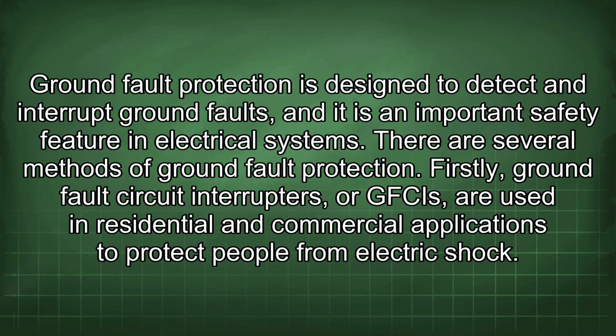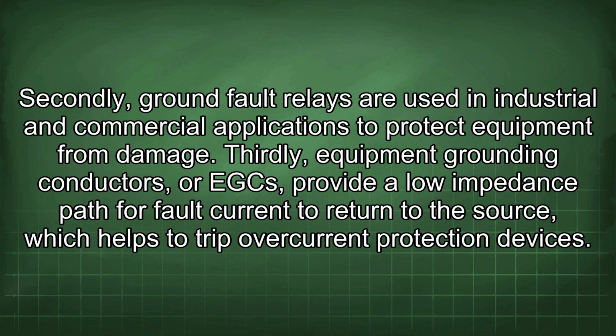Firstly, ground fault circuit interrupters, or GFCIs, are used in residential and commercial applications to protect people from electric shock. Secondly, ground fault relays are used in industrial and commercial applications to protect equipment from damage. Thirdly, equipment grounding conductors, or EGCs, provide a low impedance path for fault current to return to the source, which helps to trip overcurrent protection devices.